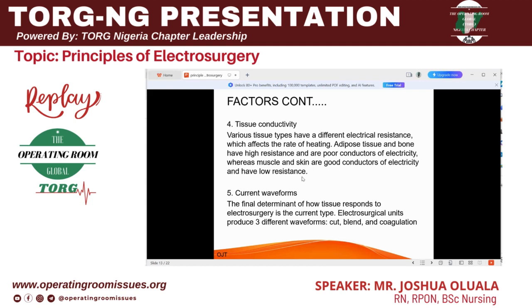Then the 5th one is the current waveform. And of course there are 5, and that's the final factor, the final determinant of how tissue responds to electrosurgery is the current type. Electrosurgical units produce 3 waveforms. We have cut, we have blend, and we have coagulation. I know we begin to cast our minds back to the diathermy we have in our various operating centers, and you begin to look. You see cut, you see blend, you see coagulation.